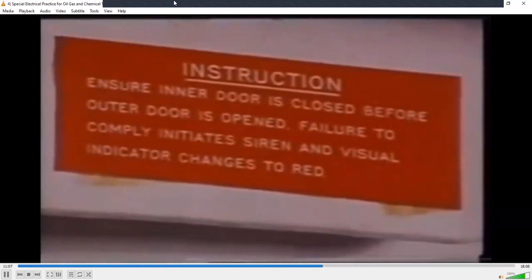The motor room is pressurized so that gas or vapor may not enter the airspace where the motors are operating. Entrance to the motor room is through a system of double doors controlled by a pair of micro switches and a safety light indicator. The system should ensure that one door is opened only when the other is shut.